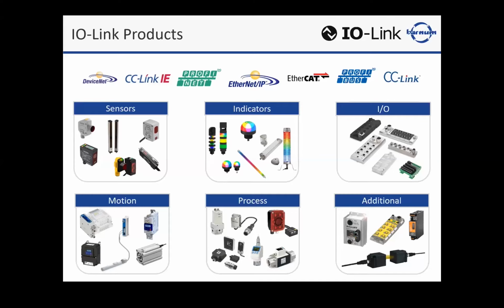Definitely. We have safety as well. I can see that in the yellow IO block on the far right. Want to explain that? Yeah, so there's actually another unique product there as well, but that yellow block indicates a safety block. Currently only available on ProfiSafe. So you need to be running a Siemens PLC, Siemens Safety PLC for that matter, using the ProfiSafe protocol. And then that block would allow you to connect your light curtains, your e-stops, your safety switches directly to that ProfiSafe IO-Link enabled block and carry that information over IO-Link.